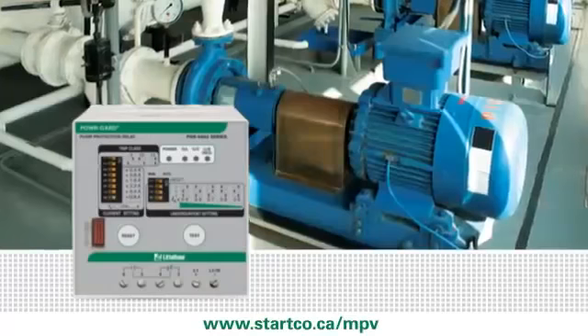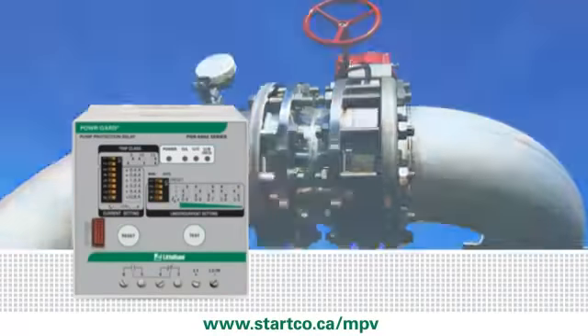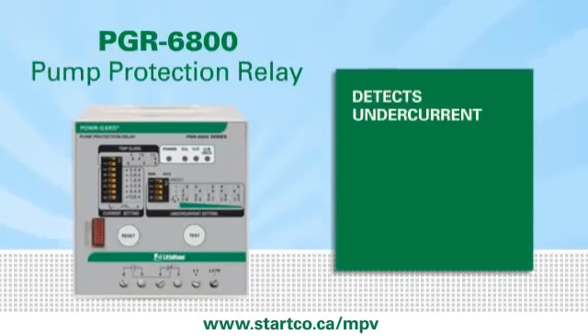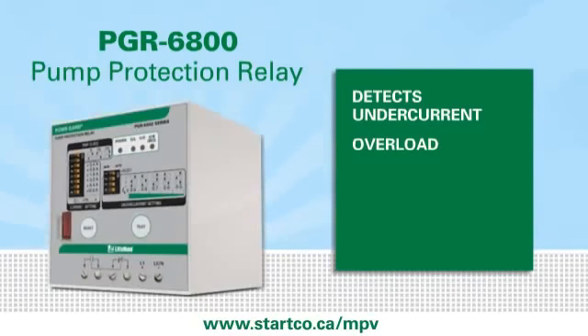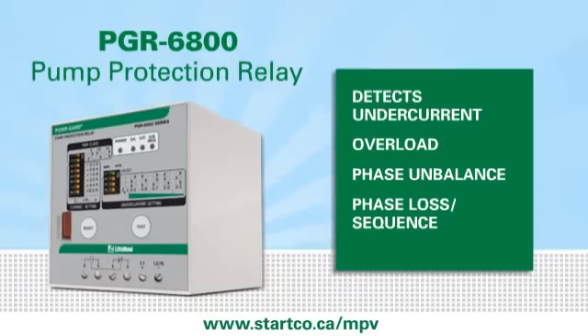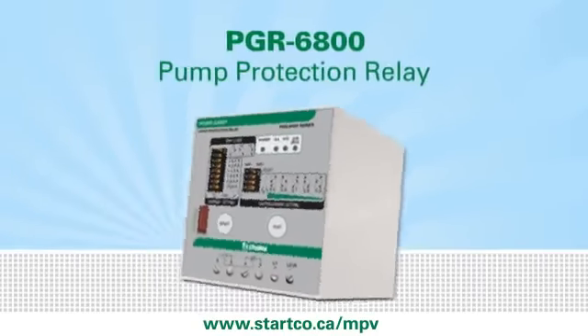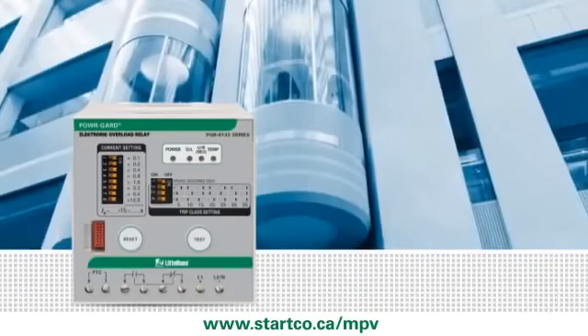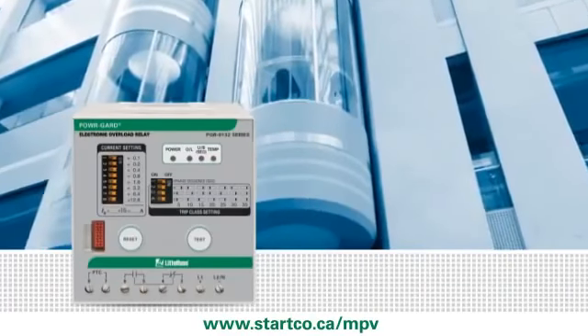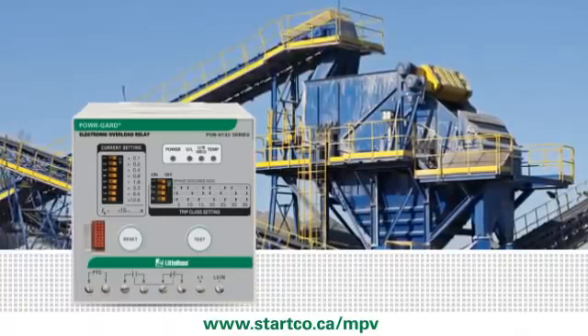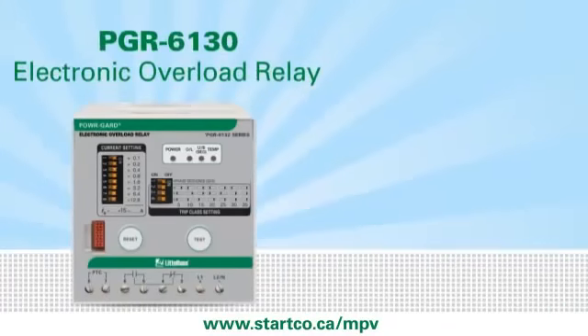The PGR 6800 offers pump-specific protection functions, such as undercurrent, and can alert if a pump experiences cavitation, which may cause overheating. This relay also prevents the common problem of stuck low-level sensors.